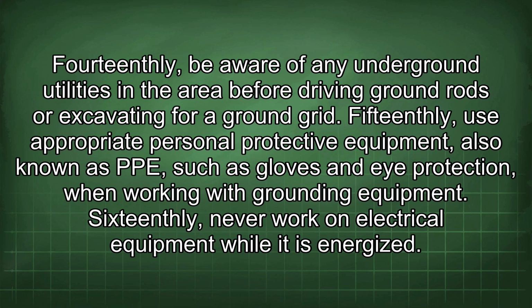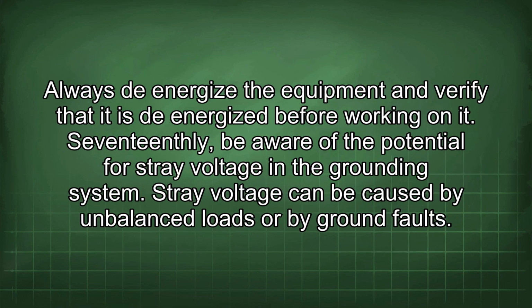14thly, be aware of any underground utilities in the area before driving ground rods or excavating for a ground grid. 15thly, use appropriate personal protective equipment, also known as PPE, such as gloves and eye protection, when working with grounding equipment. 16thly, never work on electrical equipment while it is energized. Always de-energize the equipment and verify that it is de-energized before working on it.